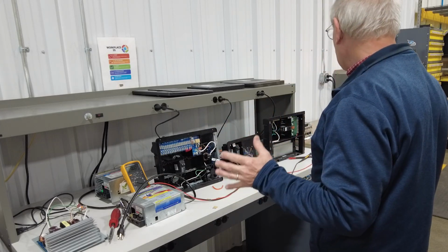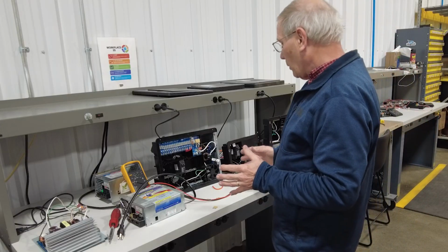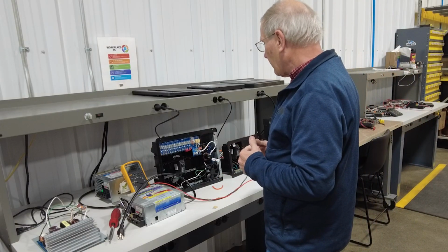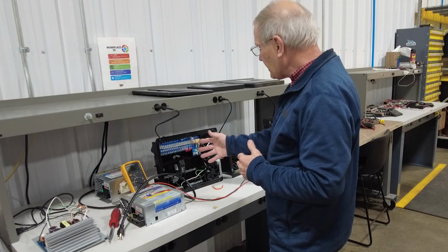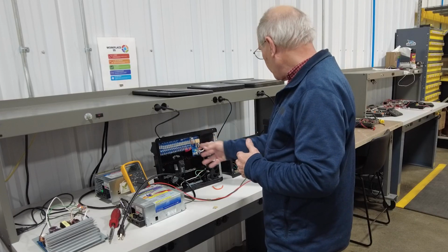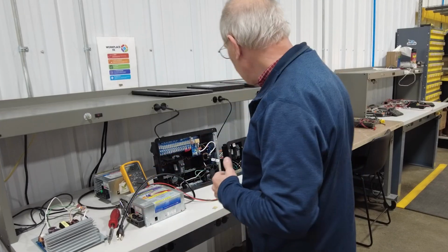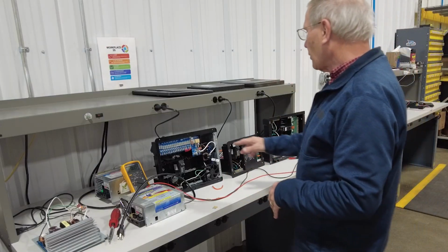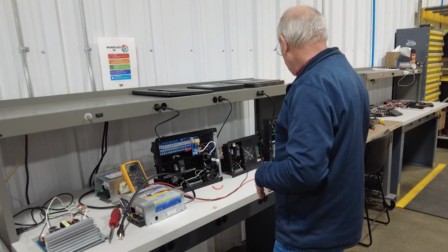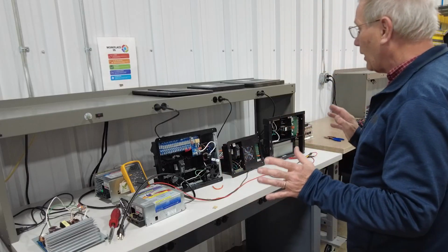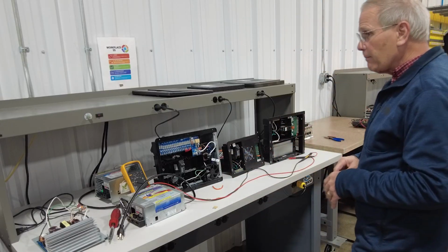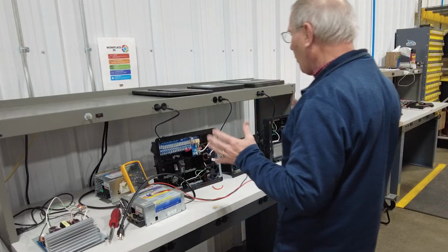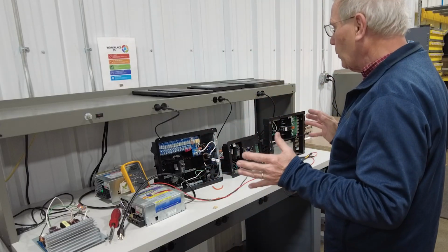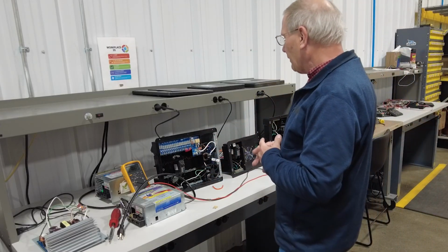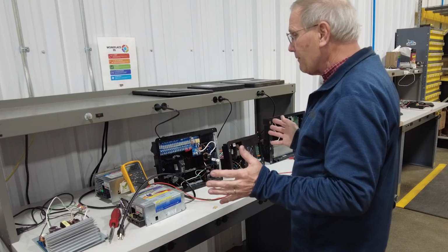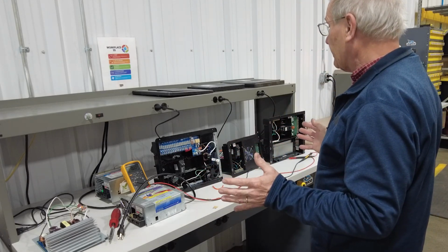So to emphasize the point, if you want to really check a power converter, you're going to do two things: disconnect the battery wires and check the voltage right at the device, and check the reverse polarity fuses to make sure they are good. You never want to send back a power converter for a warranty replacement with blown reverse polarity fuses, because that warranty claim is automatically going to get rejected.